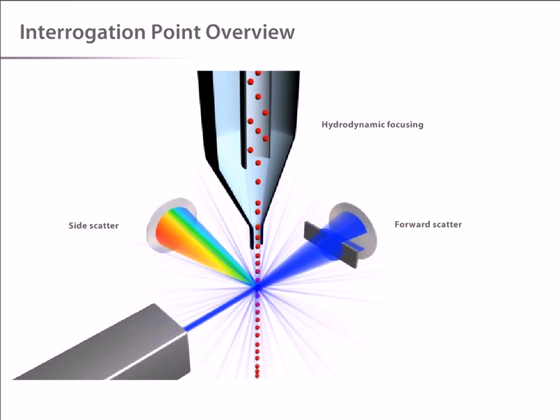The interrogation point is the heart of the system. This is where the laser and the sample intersect, and the optics collect the resulting scatter and fluorescence.